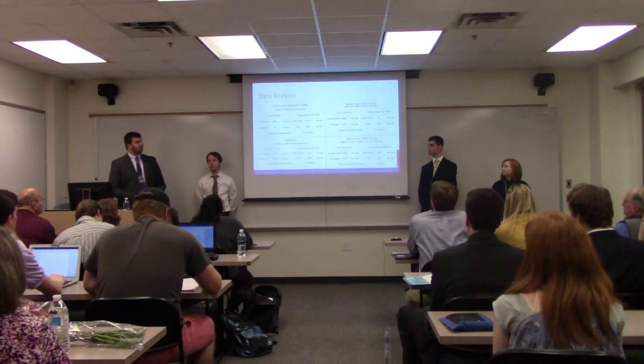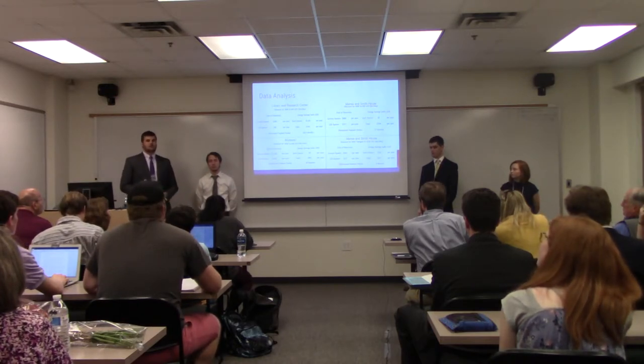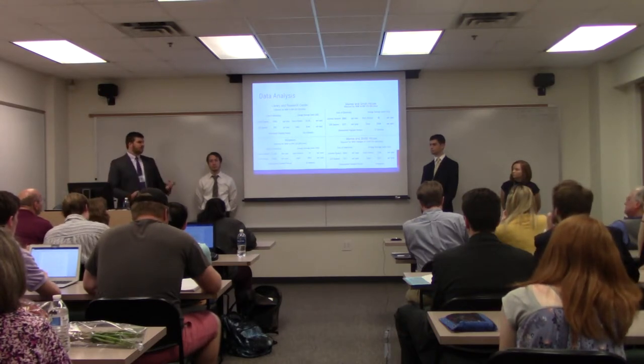Once we had all the data tabulated, we completed discounted payback analyses. For the library and research center — our beta audit building — we estimated it was used about three hours per day, five days per week. Analyzing a change from 40-watt to 8-watt LED bulbs showed a potential savings of $144 per year in energy savings, with a payback period of about 64 months. For the museum, assuming nine hours per day and five days per week, the larger scale of the building yields total savings of about $960 per year and a much shorter payback period of about 16 months.